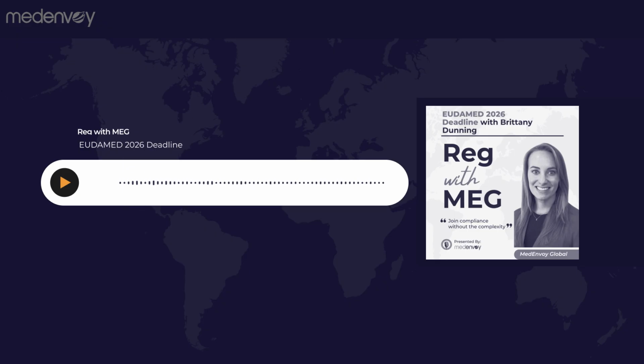Device registration requires detailed structured data. And here at MedEnvoy, we really highlight those core elements such as the basic UDI-DI and classification characteristics. And really want to note that changes to registered information may require a new UDI registered in EUDAMED. Another point to keep in mind is that custom devices, investigational devices, or devices that are currently undergoing performance studies without already having CE marking are exempt from registration at this time. So, confusion about whether a product must be registered may also cause some issues if these teams aren't clarifying the scope early.